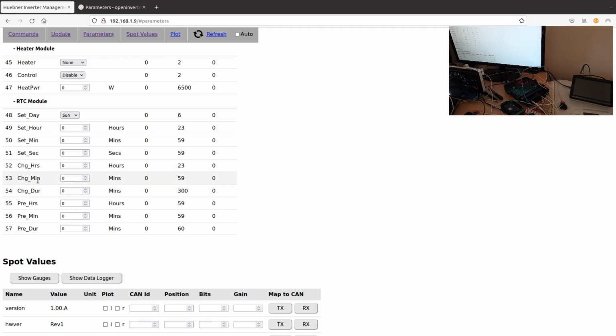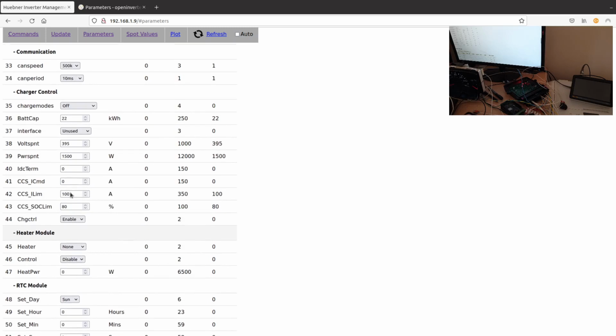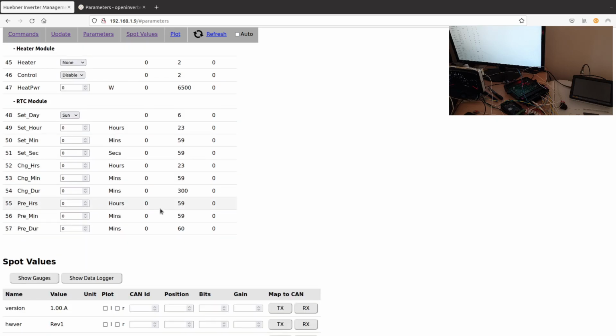Charging hours and charging minutes are the time at which we would like charging to commence. The charging duration in minutes is a safety timer, where we would like charging to terminate after a specific time if it has not already done so by means of our DC termination current set point here.